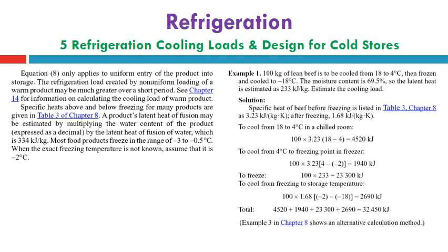the previous slide. A product's latent heat of fusion may be estimated by multiplying the water content of the product, expressed as a decimal, by the latent heat of fusion of water, which is 334 kilojoule per kilogram. Most food products freeze in the range of -3 to -0.5 degrees Celsius. When the exact freezing temperature is not known, assume it is -2 degrees Celsius. In the right part of this slide, we can find an example.